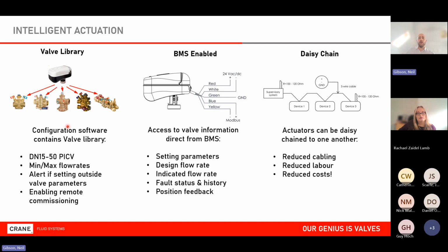Going back to the example of the Cat A, Cat B fit out. We've actually got some of these installed in a project in London. They did all of the Cat A and now they're doing Cat B, and lo and behold, the flow rates have changed. The process for them updating those flow rates is going on to the BMS and inputting a new value in the required Modbus register on a couple of dozen valves. That exercise itself can be completed anywhere from a few minutes to a couple of hours. It's not a long process. And without anyone having to physically touch the valve. No step ladders involved, no access issues. All of it's connected and already pre-configured because it's already been installed as part of the Cat A.